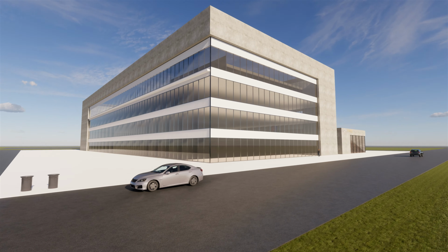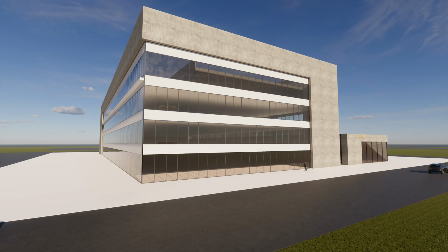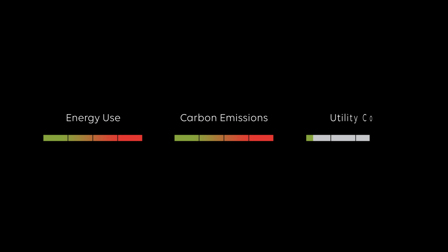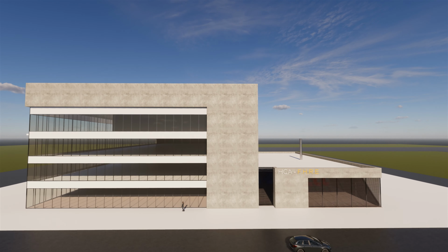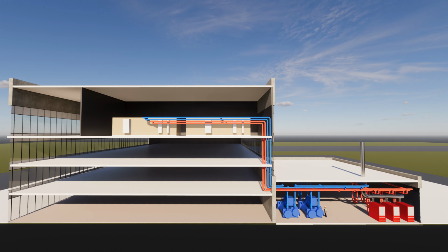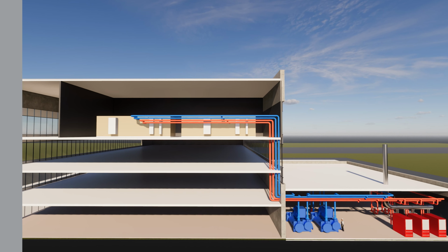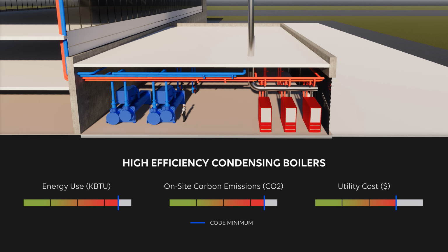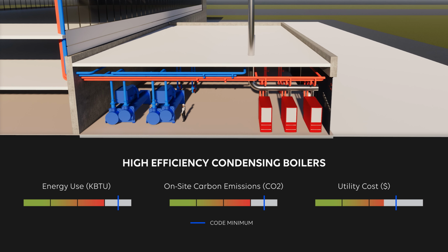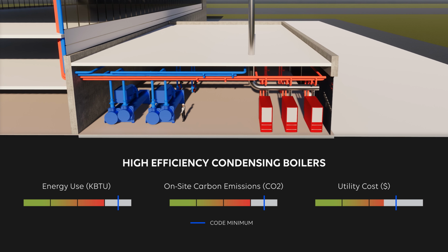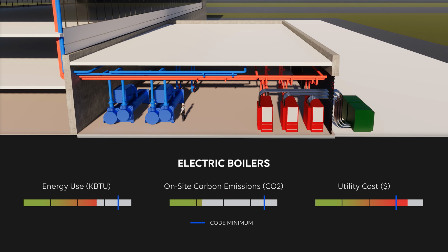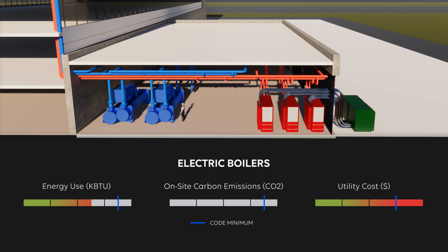The central utility plant exists to serve the heating and cooling loads. Some key performance metrics for a plant are energy use, carbon emissions, and utility costs. Let's look at a few heating equipment upgrades that achieve some combination of the reduction of these metrics. The first and most common option is to install high-efficiency condensing boilers. These boilers do reduce our three metrics when compared to a traditional non-condensing boiler, but are not the most efficient option. The next boiler option is electric, which has become very popular for clients who want to decarbonize.